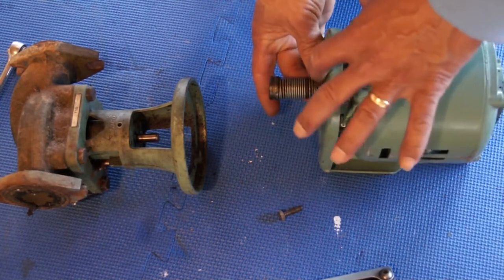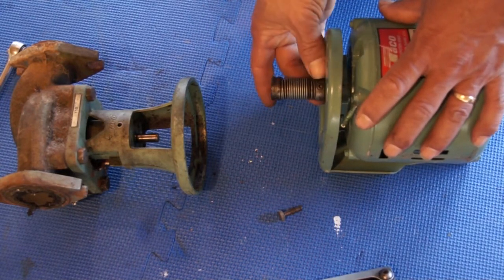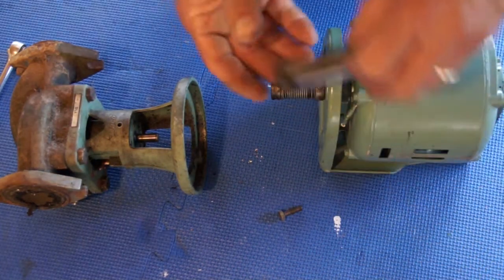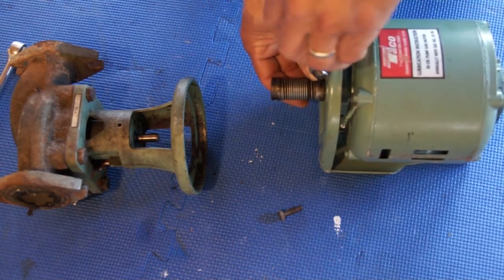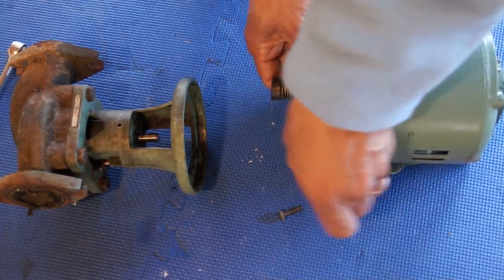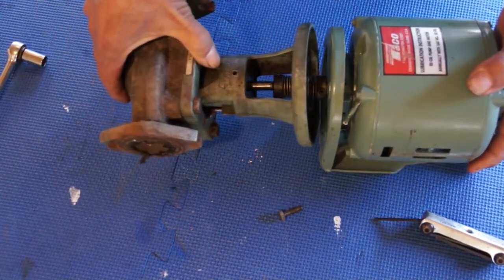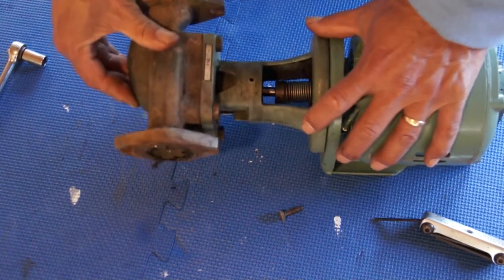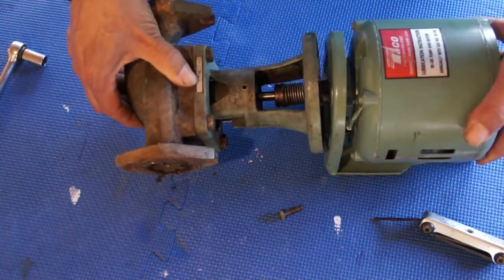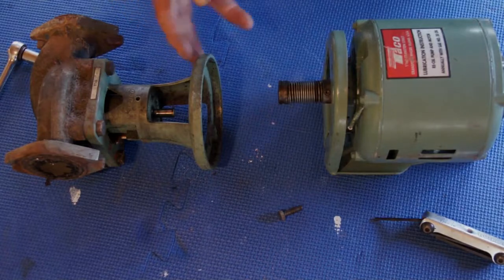You want to be level and flush with this when putting the coupling in, otherwise you won't be able to tighten it properly. About level and flush — then you should be in good shape. Tie it up, lift it up, and slide it in. As simple as that. Get the screws in, find where the holes are, and that's it guys — two screws, that's all. You only need a 7/16 wrench.